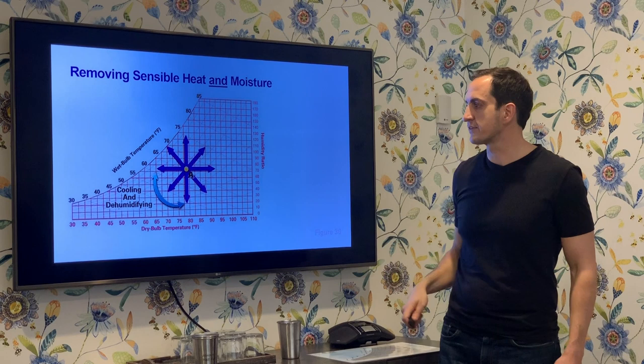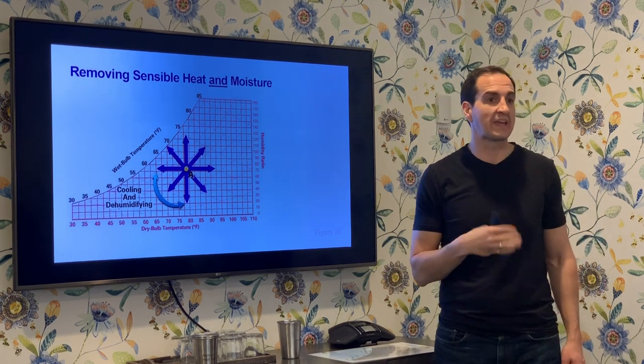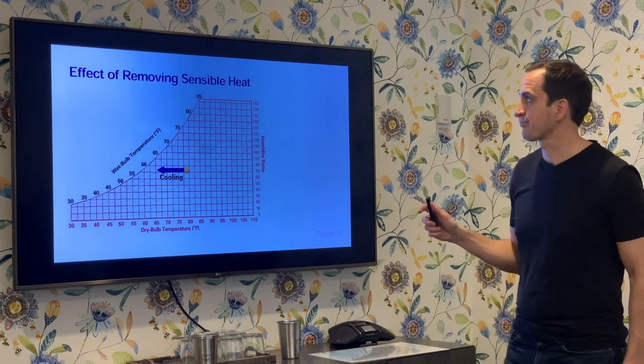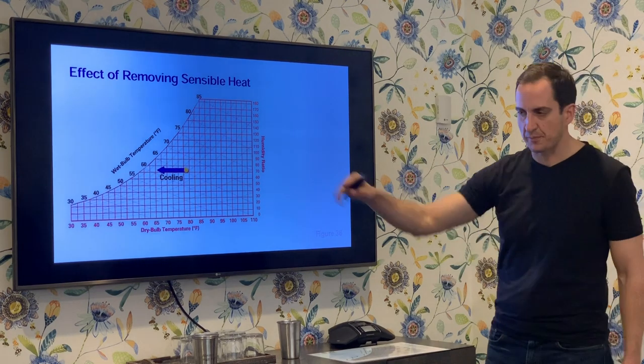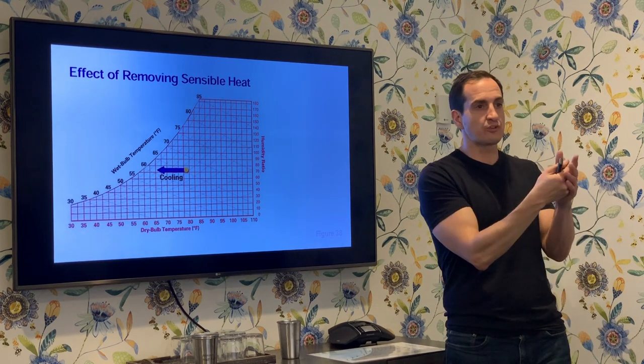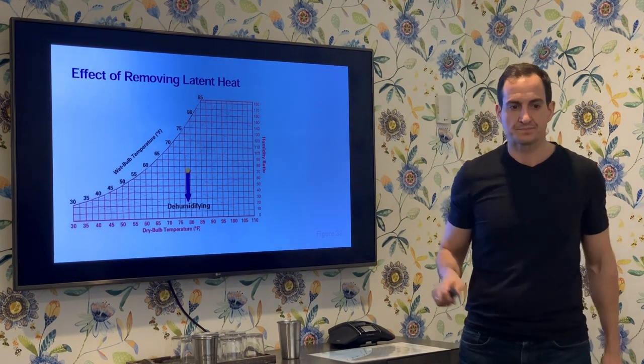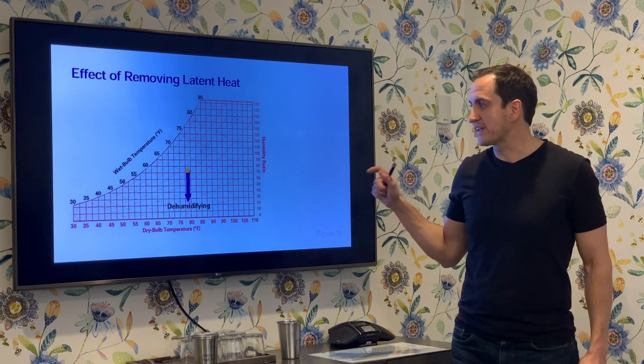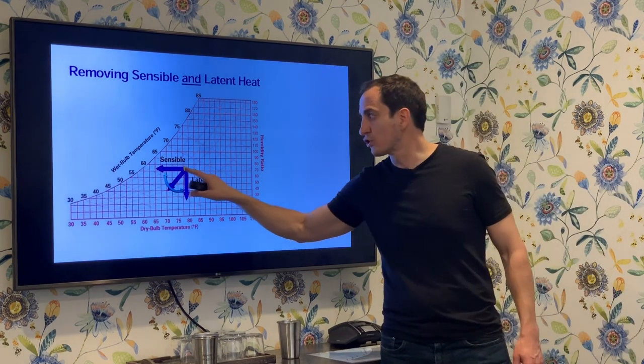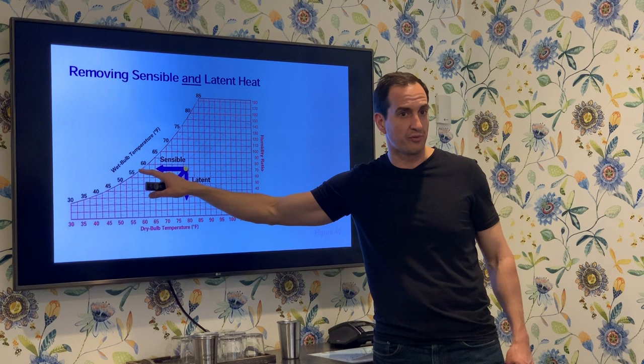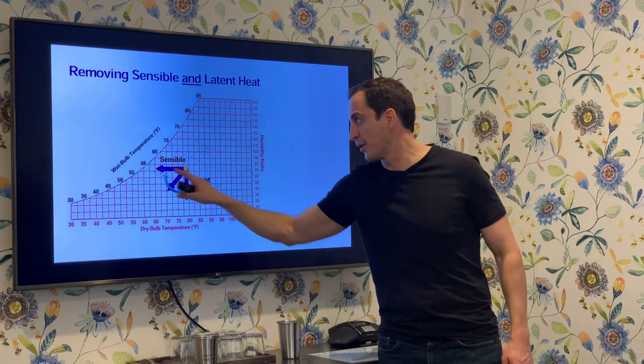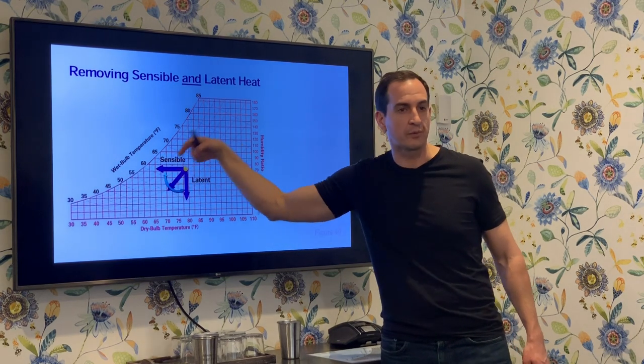You can go in any combination of directions following these lines. Cooling and dehumidifying is what most mechanical air conditioning systems do — including desiccant systems. When we remove sensible heat and cool air by introducing it to a surface colder than the dew point, we cool it below the condensation temperature, condensation forms on the cooling surface, and we end up doing sensible and then latent cooling — moving in that direction.